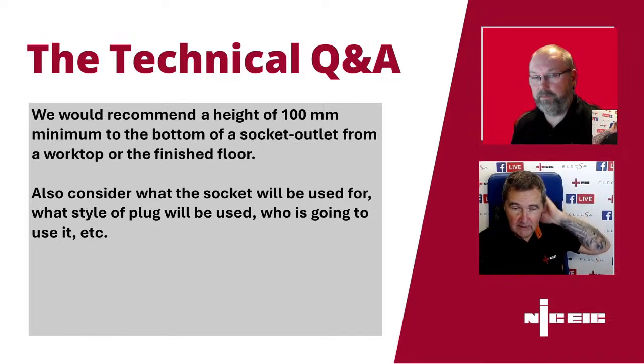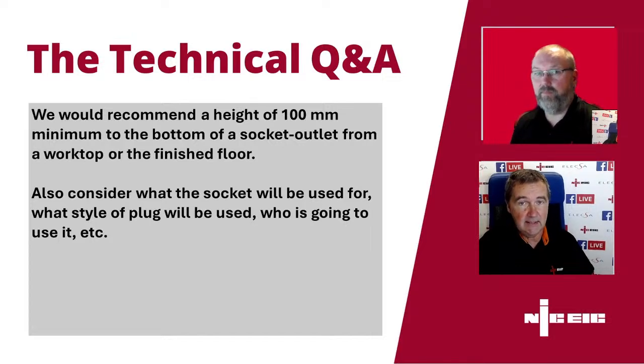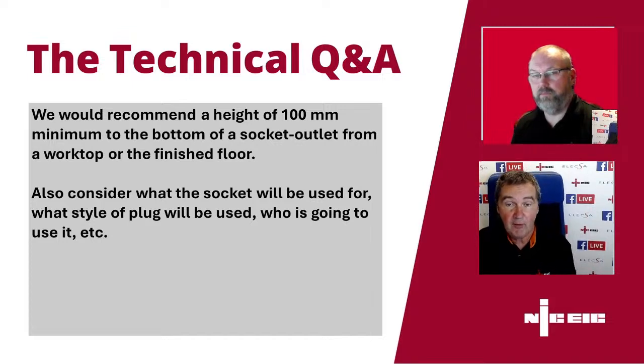Yeah, it's all about whether the cable is provided with adequate protection for the environment it's installed in, going back to one of our fundamental principles, that everything should be suitable for the installation in which it's installed, or the way we're installing it should make it suitable. So as Craig said, if it's not likely to be impacted from above, you may be able to provide some form of containment that doesn't have a covering above the cable. There's nothing that explicitly rules unistrut out from being used as containment, but it needs to be suitable for the environment it's installed in.